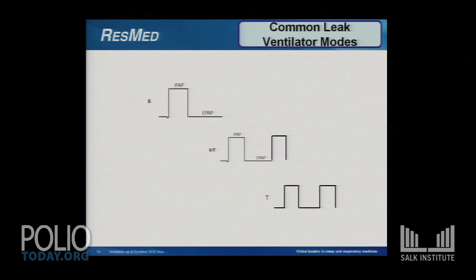Now you can see this breath was triggered by the patient, right? So we came from our EPAP up to our IPAP. But this breath over here was triggered by the machine because it waited a certain amount of time and there was no effort by the patient. So the machine stepped in and gave that breath for the patient. So you've got that safety and security. If you were to quit breathing during sleep, the machine is going to ventilate you without you having to worry about it.